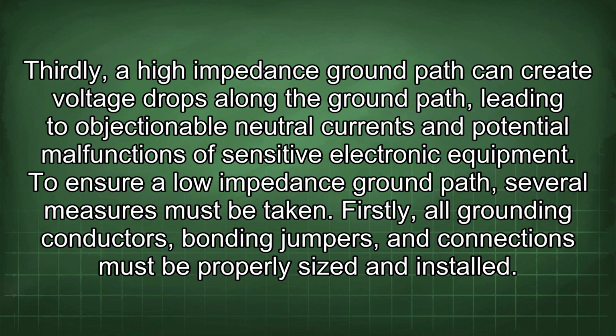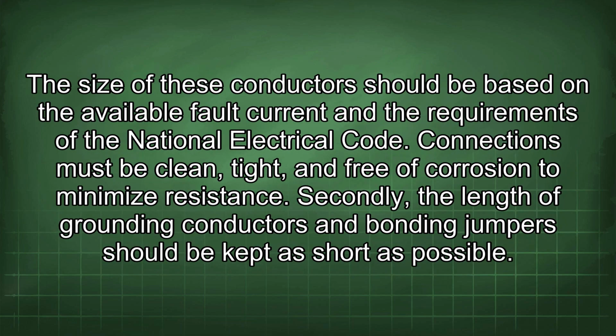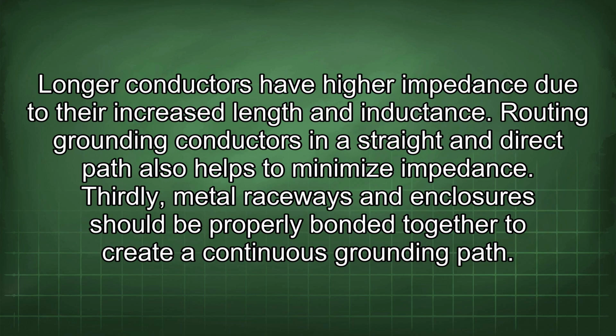To ensure a low-impedance ground path, several measures must be taken. Firstly, all grounding conductors, bonding jumpers, and connections must be properly sized and installed. The size of these conductors should be based on the available fault current and the requirements of the National Electrical Code. Connections must be clean, tight, and free of corrosion to minimize resistance. Secondly, the length of grounding conductors and bonding jumpers should be kept as short as possible. Longer conductors have higher impedance due to their increased length and inductance. Routing grounding conductors in a straight and direct path also helps to minimize impedance.